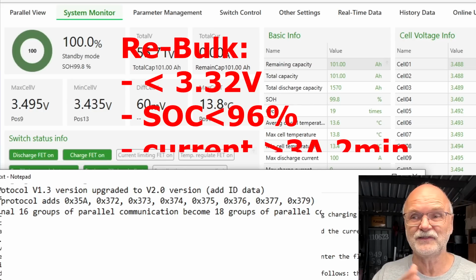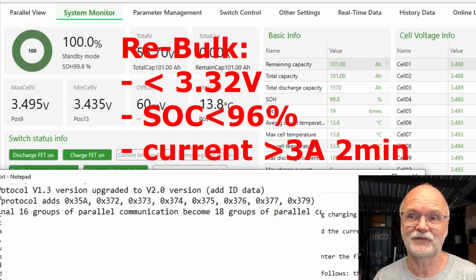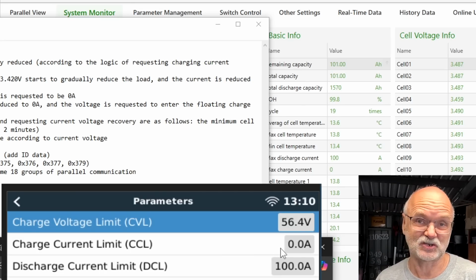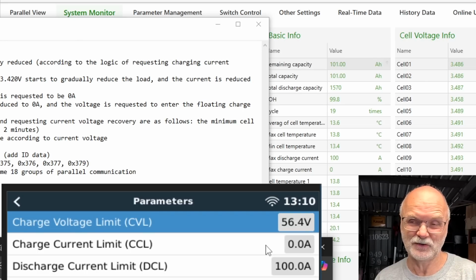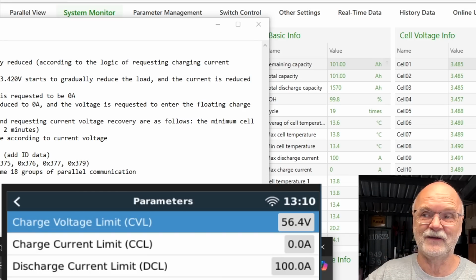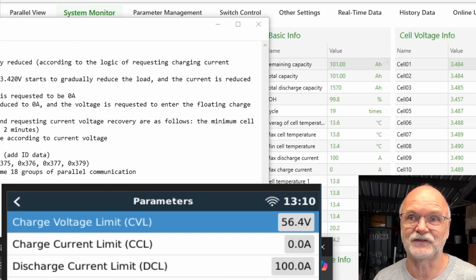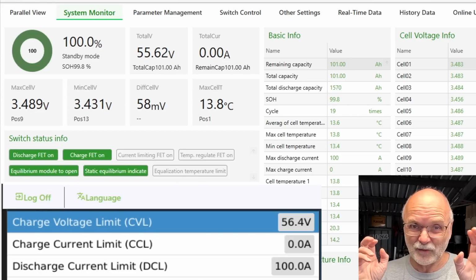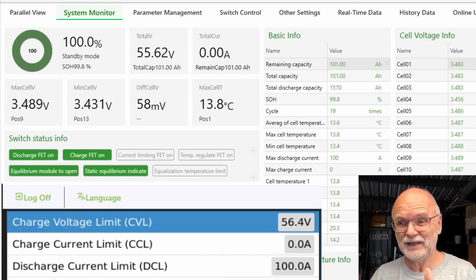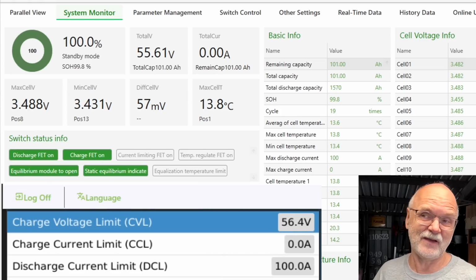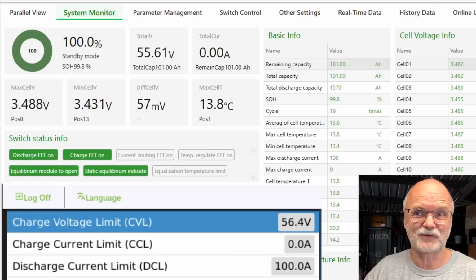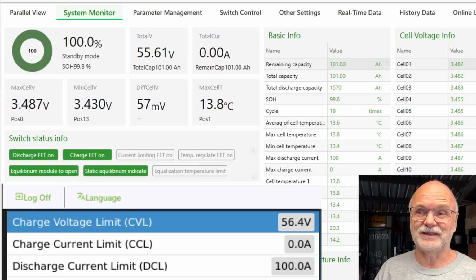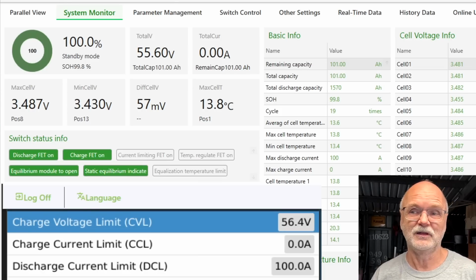The third condition is if we have a discharge current of more than 3 amps for 2 minutes. This would then tell your inverter to start charging again, and it takes the voltage you have in your battery and sets the CCL accordingly. If you're still at 3.45 volts or so, it would reduce it, as we've just seen. So we've got a float situation now, but only because there's no load connected here at the moment. If you have an inverter connected with some load on the battery, it will discharge it, and if the current goes over 3 amps, which is only 150 watts for 2 minutes, it will recharge the battery and keep it at whatever voltage you have set.